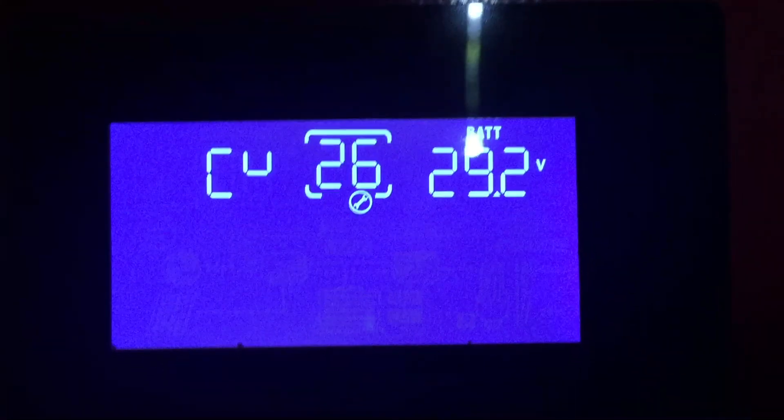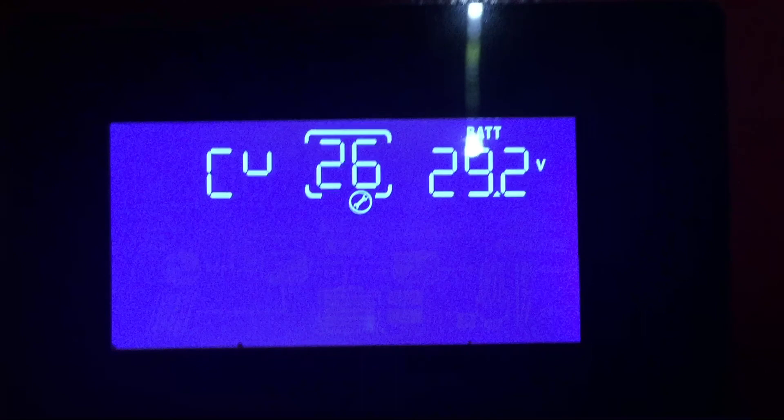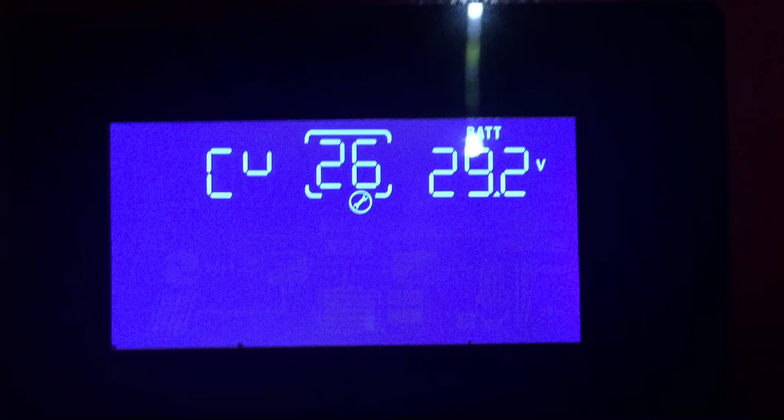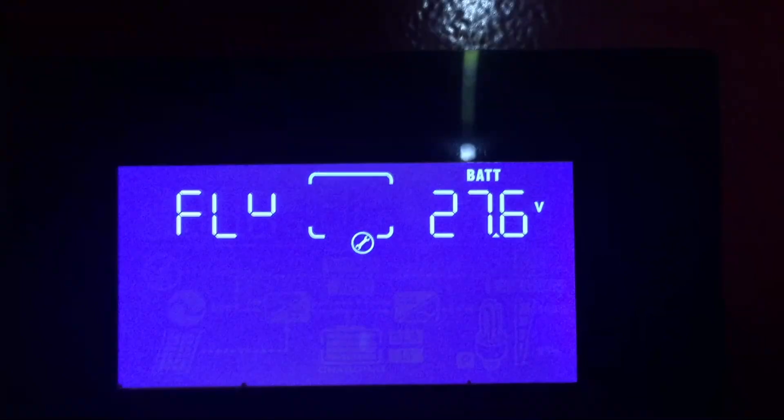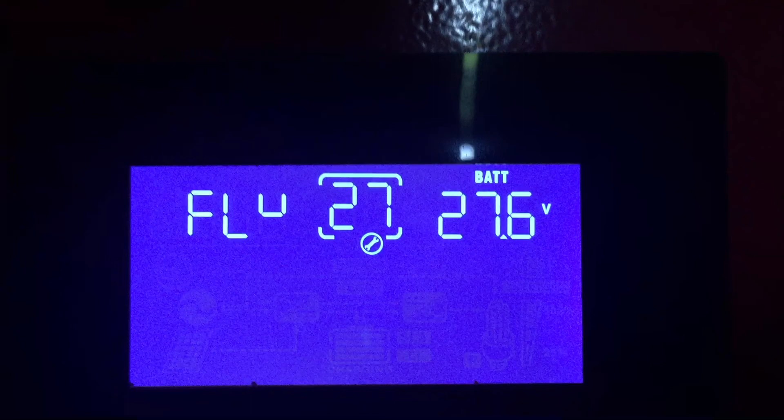Number twenty six, this is where you can program your bulk charging voltage. In my particular case gel battery I'm at twenty nine point two volts. It may vary in case you have a different battery. In twenty seven this is where I program my float voltage. In my case again the gel battery is at twenty seven point six volts. Yours may also differ.